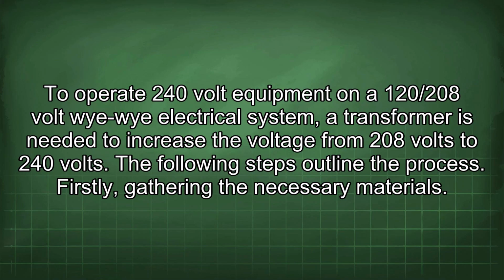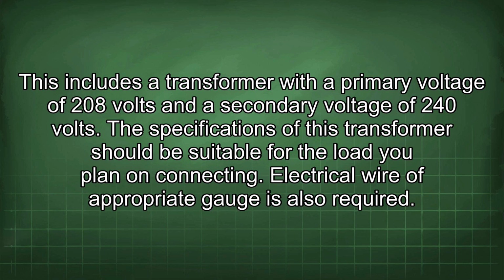To operate 240-volt equipment on a 120/208-volt wye-wye electrical system, a transformer is needed to increase the voltage from 208 volts to 240 volts. The following steps outline the process. Firstly, gathering the necessary materials. This includes a transformer with a primary voltage of 208 volts and a secondary voltage of 240 volts. The specifications of this transformer should be suitable for the load you plan on connecting.